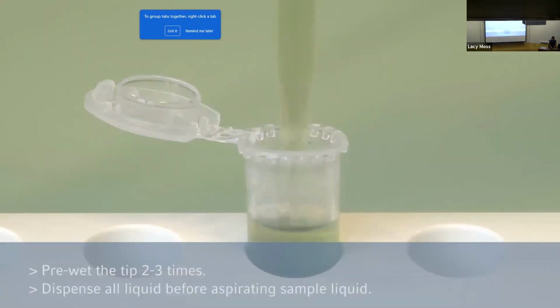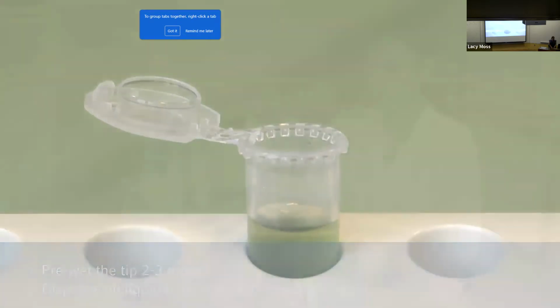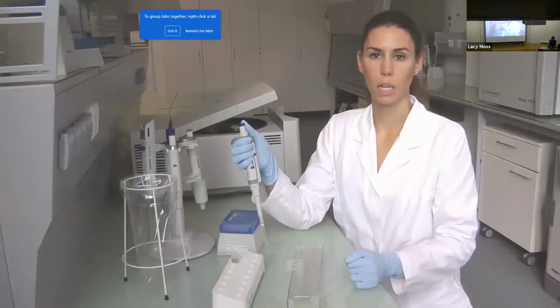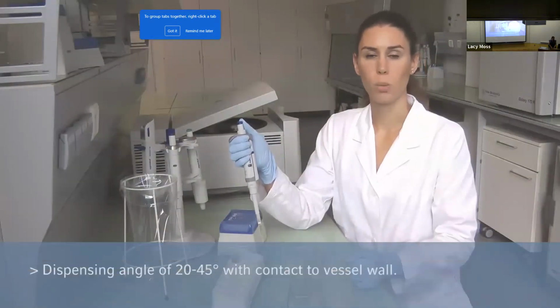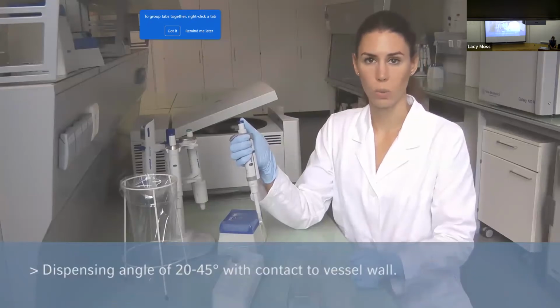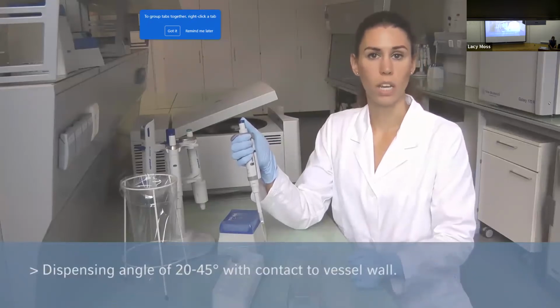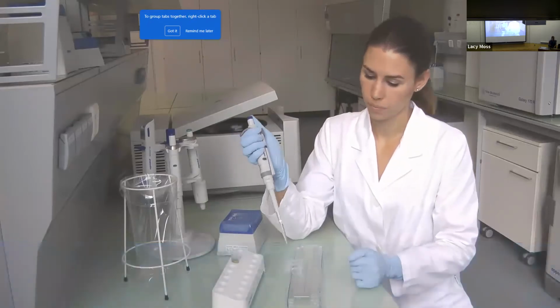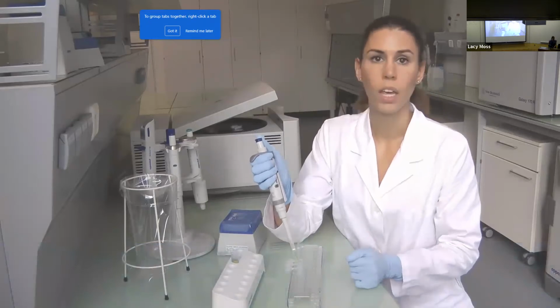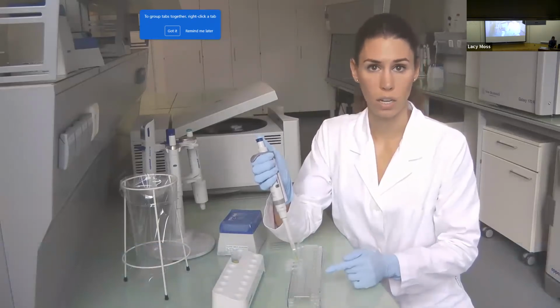Repeat this 2 to 3 times to saturate the air in the tip. When dispensing liquid, the angle of the pipette should be between 20 and 45 degrees, whilst the tip should stay in contact with the vessel wall. This guarantees optimal flow out of the liquid into the target vessel.